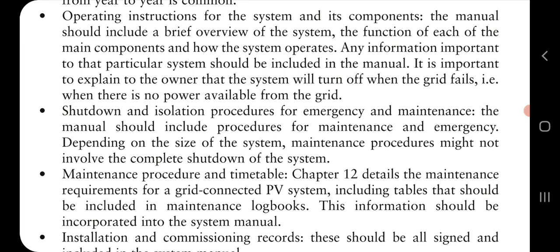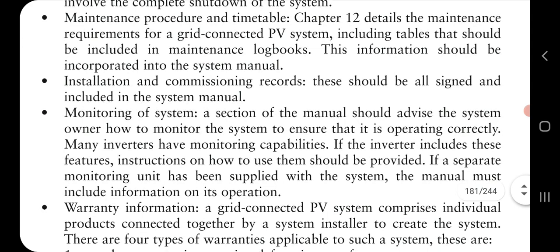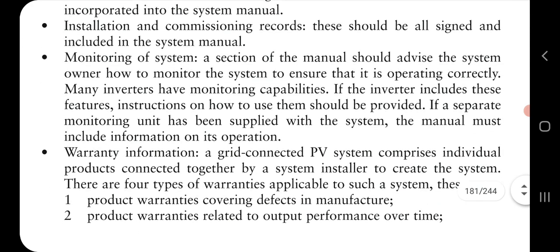The maintenance procedure is also very important. They have to give the various maintenance tasks. Then installation and commissioning records: whatever they have done and whatever testing they have done, they have to give, with signatures. Monitoring system: the inverter has to be monitored properly, so the manufacturer has to provide the monitoring manual to the owner so that it can be monitored.